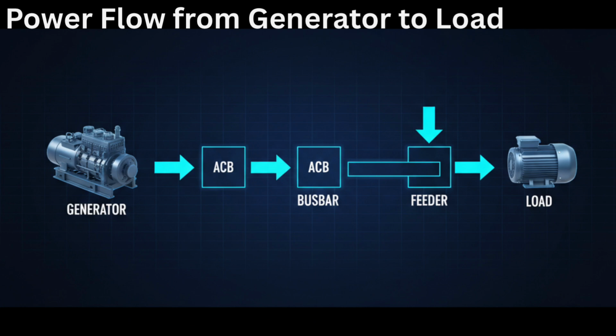After checking voltage and frequency, the air circuit breaker is closed. Once the breaker closes, power flows into the main bus bars. From the bus bars, power is distributed to feeder breakers. These feeders supply motors, pumps, compressors, navigation systems, lighting, and accommodation loads. So the complete power path is generator to ACB, ACB to busbar to feeder breaker, and finally to the load.